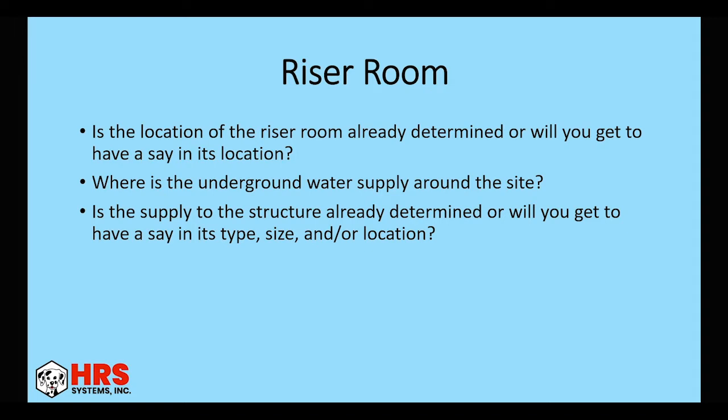Then is the location of the riser room already determined or will you get to have a say in where it's going? If they put the riser room in the back of the building and the underground is coming into the front, obviously you're going to have to run new underground around the riser. So that's going to decrease your water supply. Also, again, if you can loop it, then you can put the riser in the best hydraulically demanding place. And then do you get to have a say in the pipe that's being used? So PVC, ductile iron, these things can all help. Again, also size is a major issue. So if you can have a say in all these things, your water supply is going to be better and could help you get around having a pump. But if these are all already determined, you're kind of stuck with the choices that have been made for you.